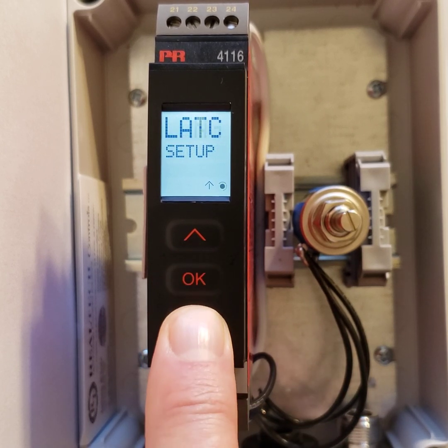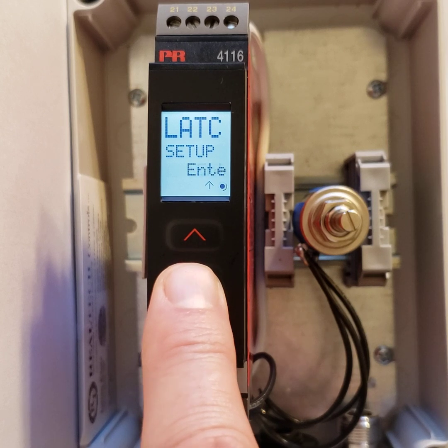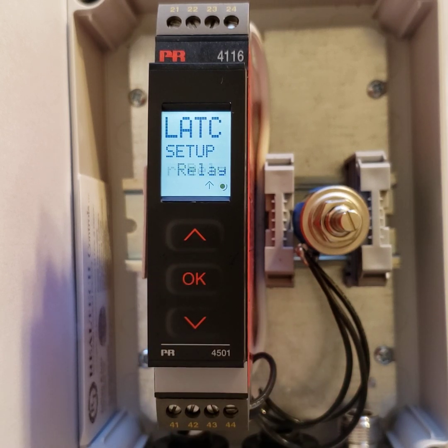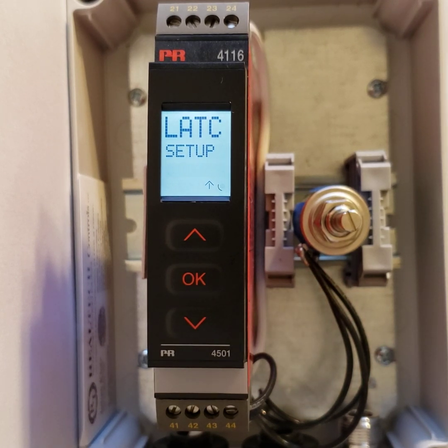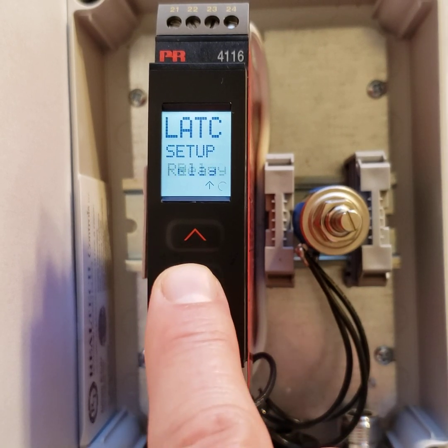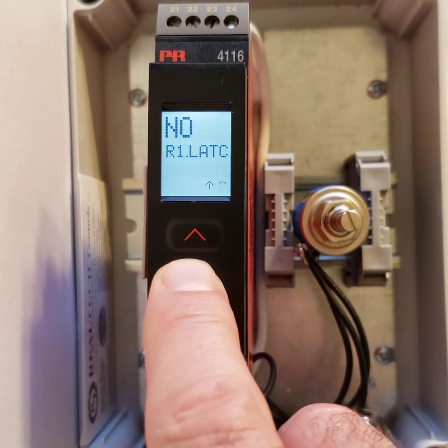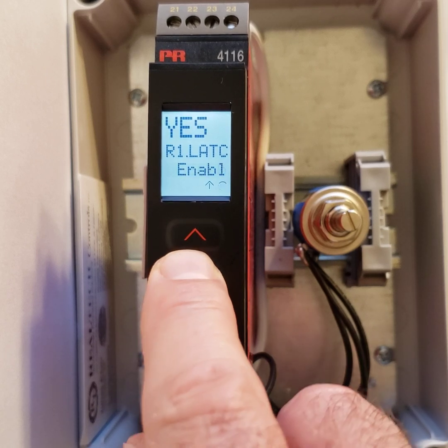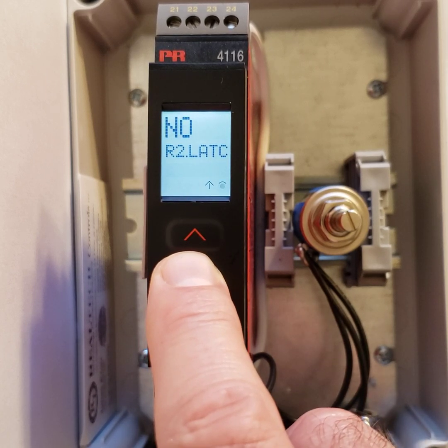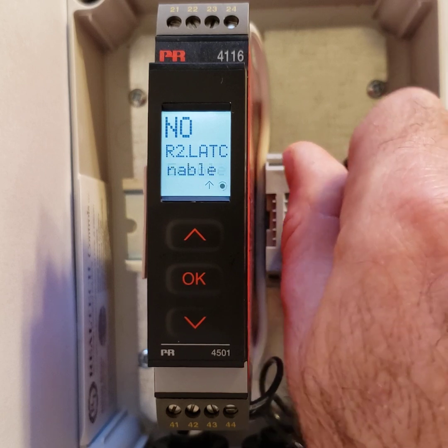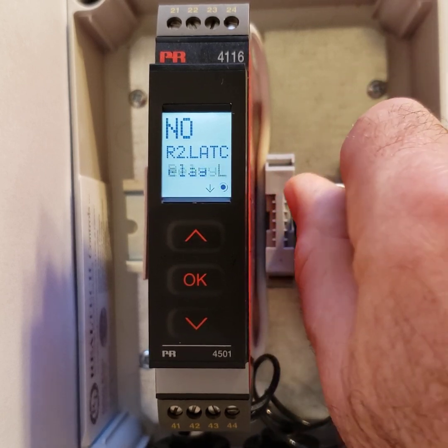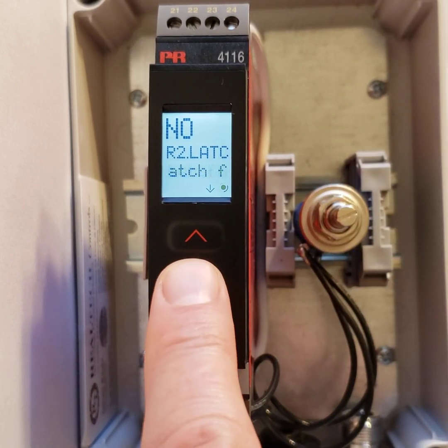The next function is latch. What latch does is if your relays turn on and it's a critical process that you don't want them to just reset when it goes below the set point of the relay and you have to have human intervention, this is how you can set it up for a critical function. We're going to choose relay one, latch, yes. Relay two, latch, no. I'm just going to make sure that my relays are not on, so I'm just going to turn the pot down.